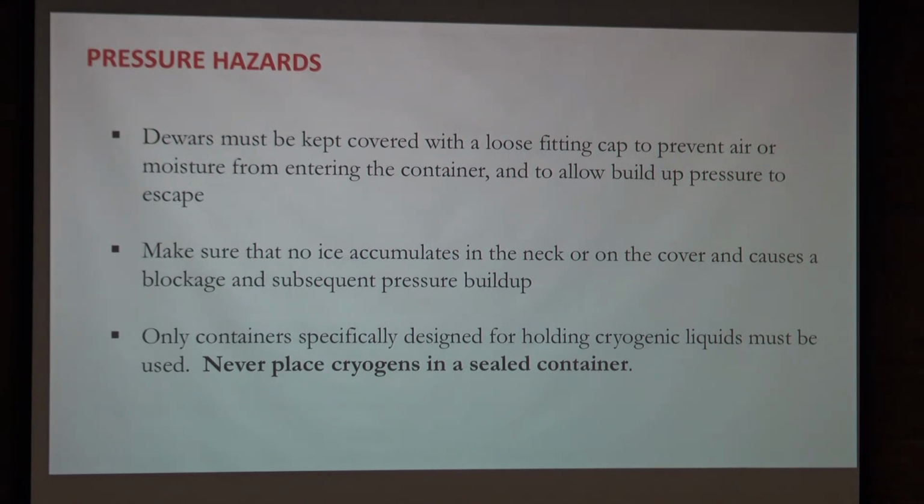You want to keep the neck of your dewars always free from ice or any other gases that can freeze and cause blockage. The blockage could then block the gas from escaping, with a consequential build-up of pressure. Basically, only use proper containers that are actually designed for keeping cryogenic liquids. Never place cryogens in a sealed container that does not provide any means of escape.